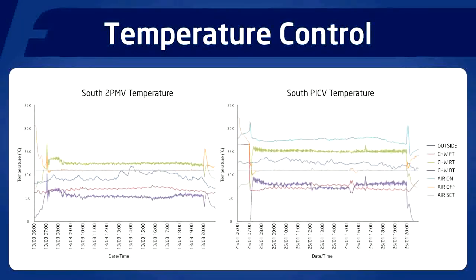The next graph compares the same data collected on the south air handling unit, but on different days, when fitted firstly with a conventional valve and secondly with a pressure independent control valve. It can be seen here also that the water delta T, the difference between the supply temperature and return temperature, is higher when a pressure independent control valve is fitted to the same air handling unit than with a conventional two-port modulating valve.